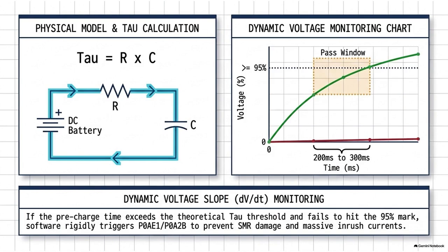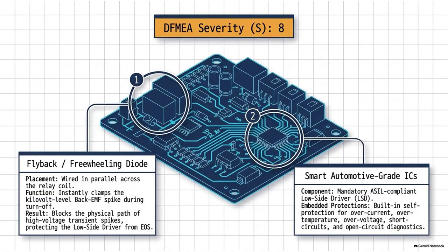Exactly. The formula is tau equals R times C. Time constant equals resistance multiplied by capacitance. The architecture doesn't just look to see if current is flowing, it analyzes the exact rate of the voltage climb across that DC link capacitor. So if the engineering team specifies a 30-ohm resistor and a 1,000 microfarad capacitor, physics dictates an absolute unchangeable curve for exactly how fast that voltage should rise. Precisely. And the BMS software is programmed to monitor that specific slope.